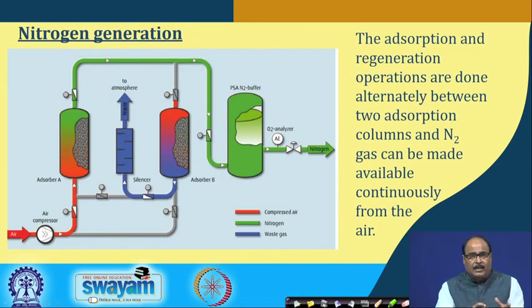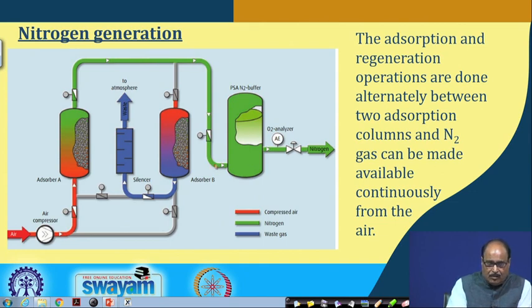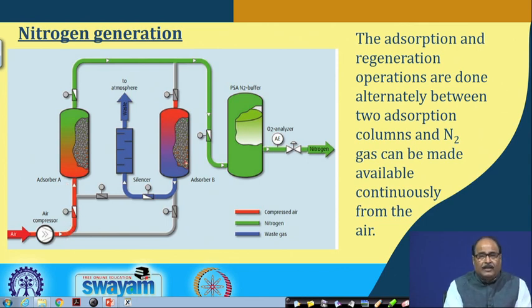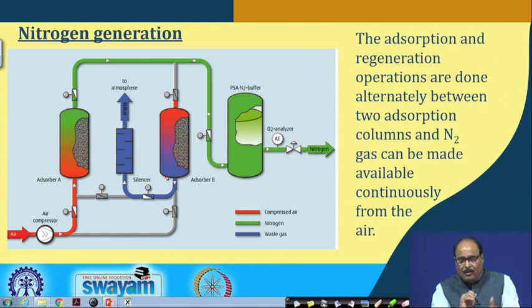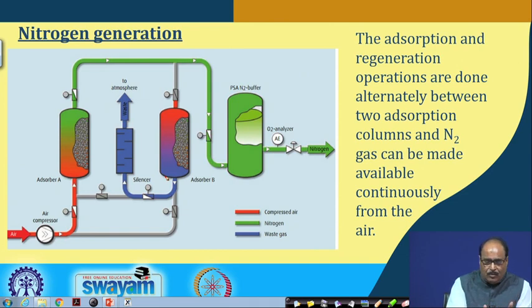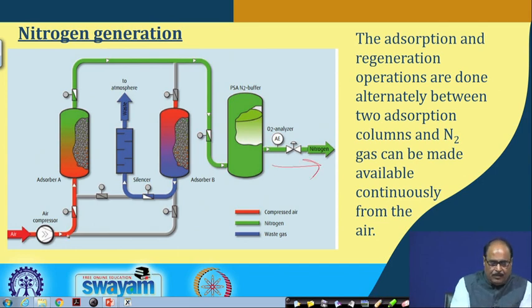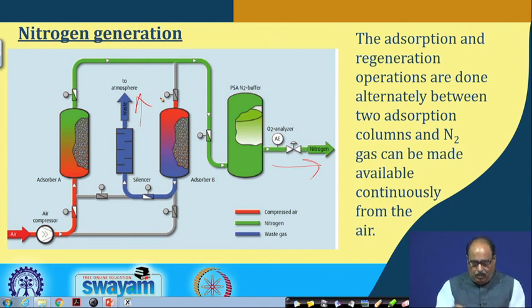As you can see in this figure of the nitrogen generator, the nitrogen gas (shown in green) is produced as compressed air (shown in red) enters through two adsorbers. The adsorption and regeneration operations are done alternatively between the two adsorption columns so that nitrogen gas is made available continuously from the air, while waste gases are allowed to escape to the atmosphere.